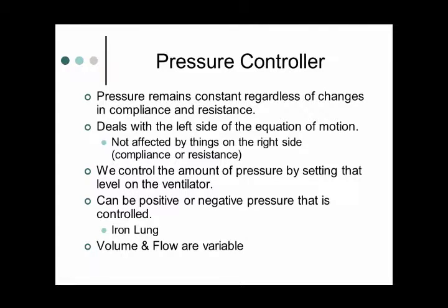It will not respond to changes in compliance and resistance. It will continue to deliver that pressure at that level until the end of the inspiratory time. However, there are safeguards built into that. So if the patient coughs against it, yeah, they can generate a higher pressure than what is set, and that will terminate the breath at that point. But that's, again, outside the normal, what we're talking about.